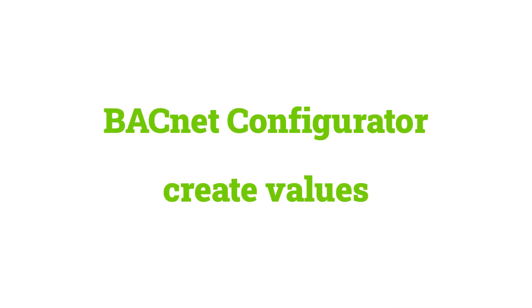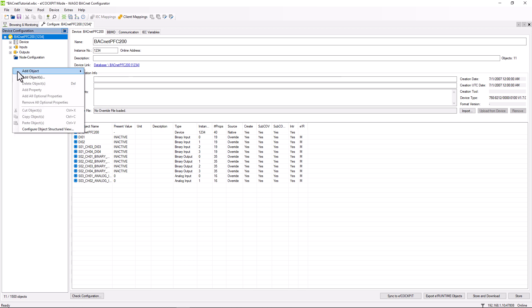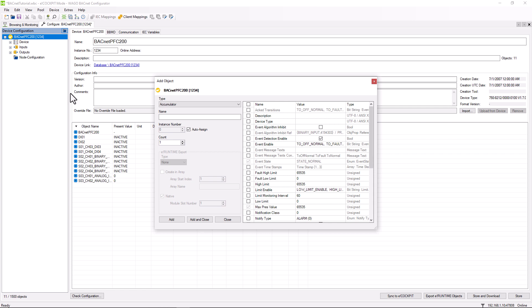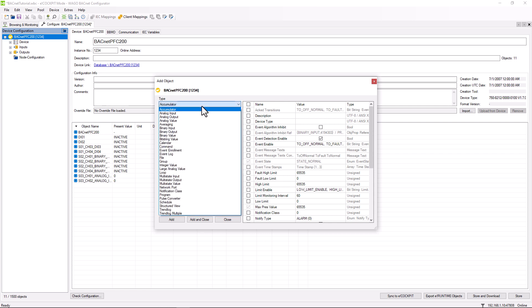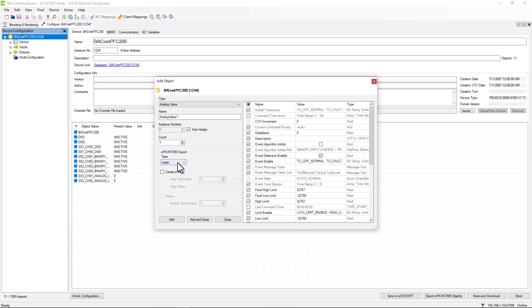Now we want to create an additional non-native value that is not directly linked to an input or output. To do this, we right-click in the structure view on the left and select 'Add Objects'. In this window, we select the object type 'analog value', give it a name, and select medium. If you are not sure which property you need, you can see how the checkboxes in front of the properties change as you select the different properties in the right-hand window. We will stay with medium and confirm with 'Add and Close'.